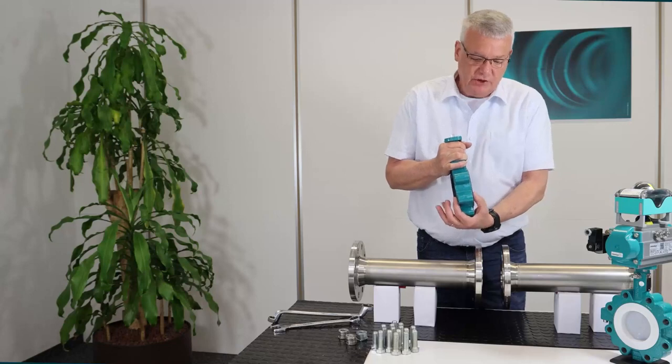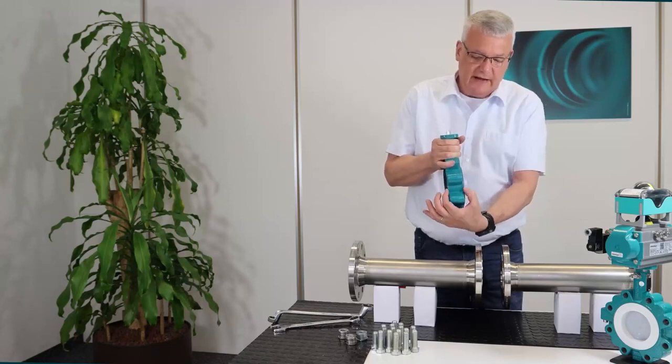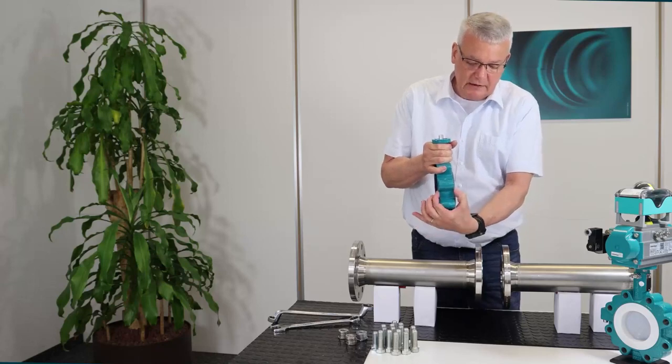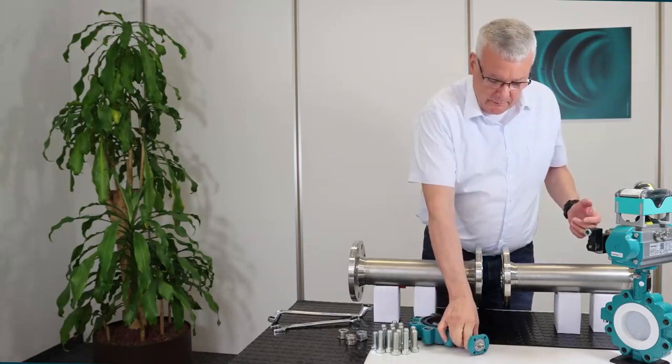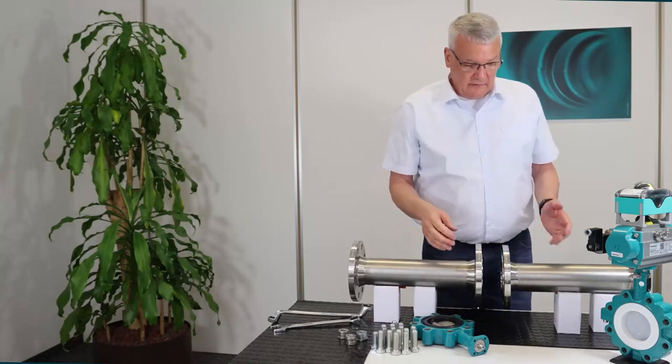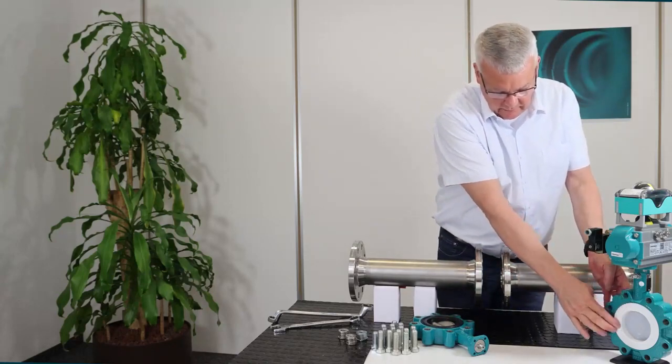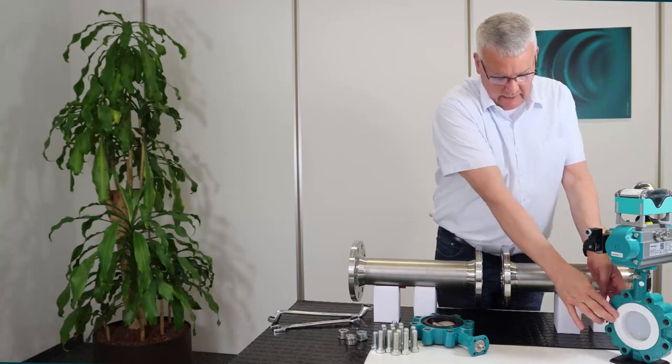The face-to-face dimension of a rubber-lined butterfly valve is the edge of the body, so this line here, whereas on the PTFE-lined butterfly valve, the face-to-face dimension is the flange surface of the liner that you see here.